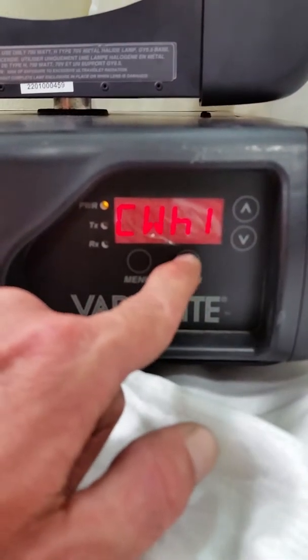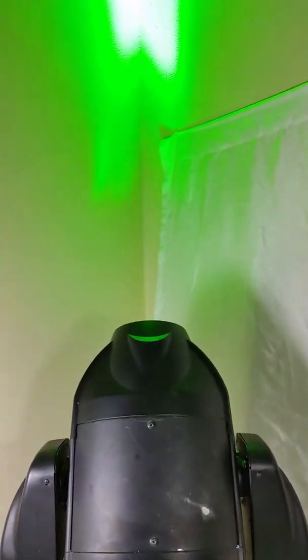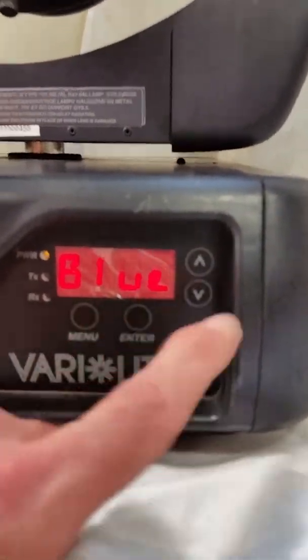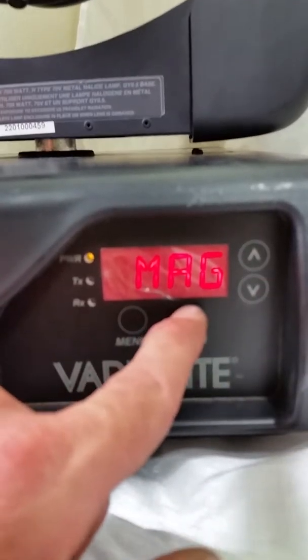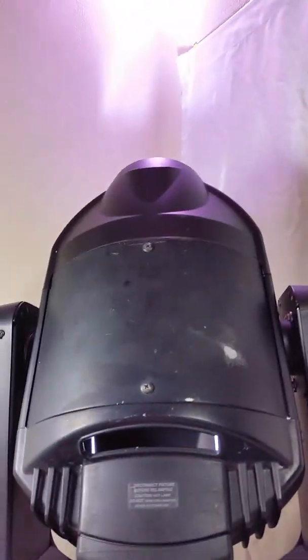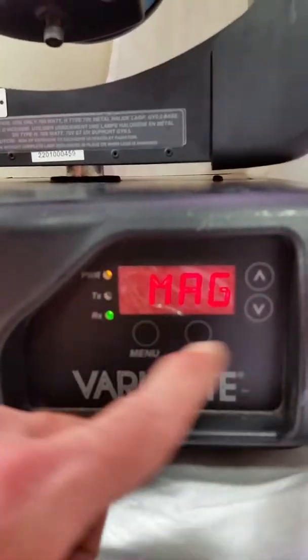So you go to menu and you go to color, and you have to pass. You can check individual colors and each color will pass. We are doing this to simply show the device is in calibrated and functional condition without a console being attached to the device.